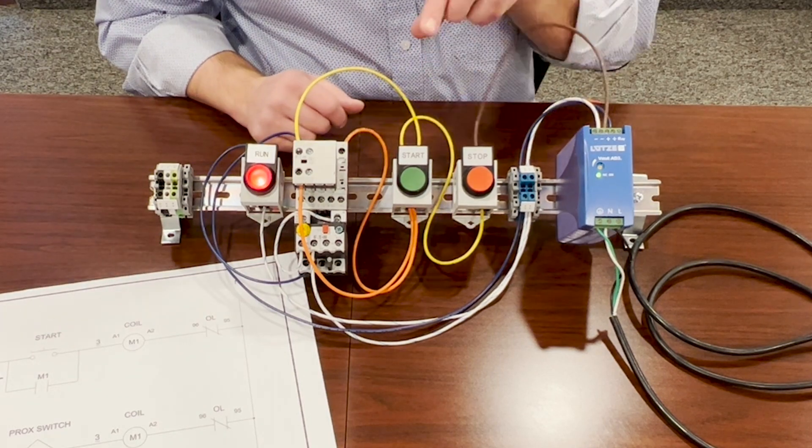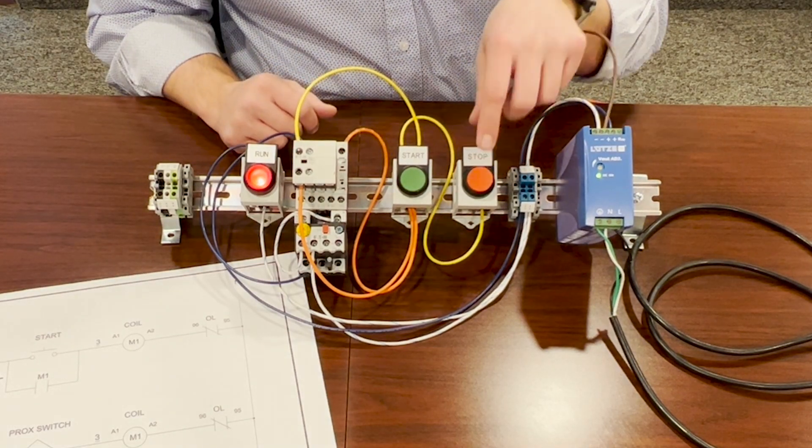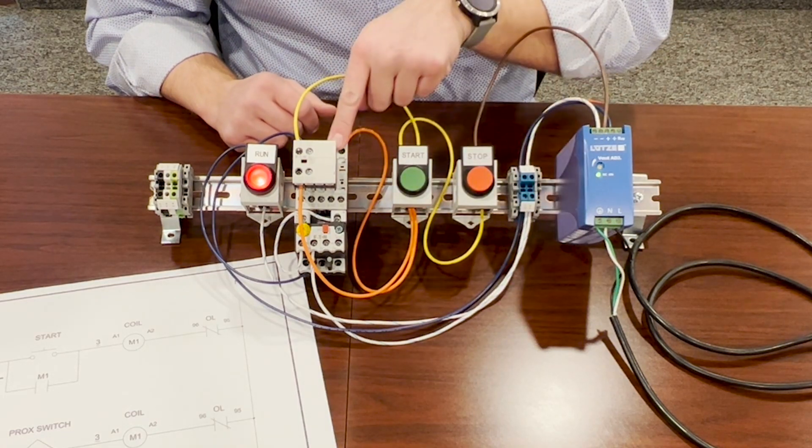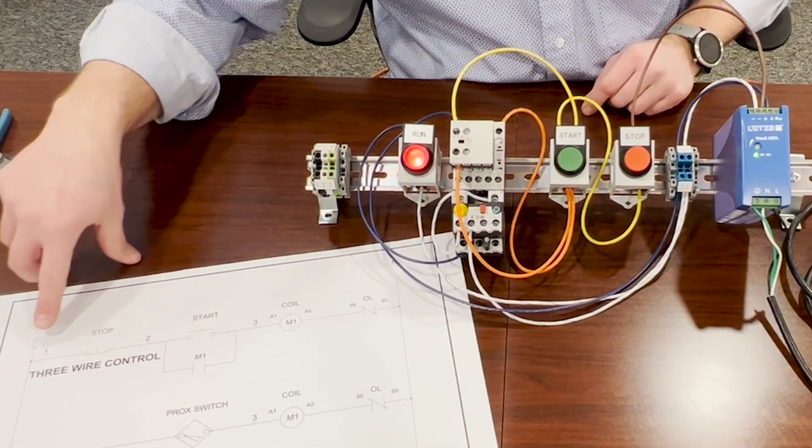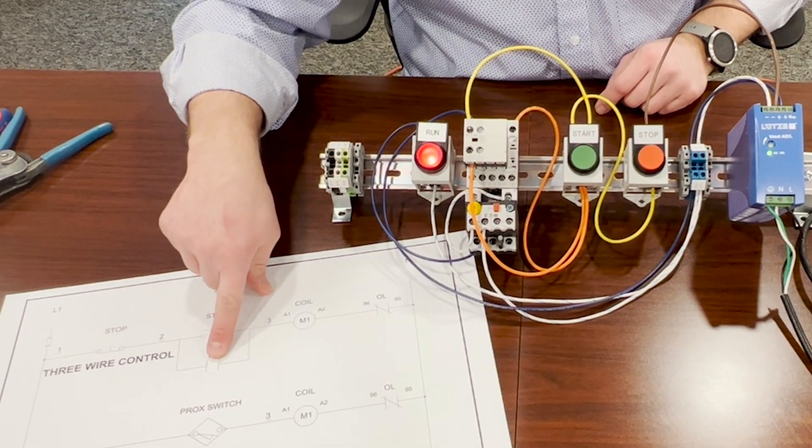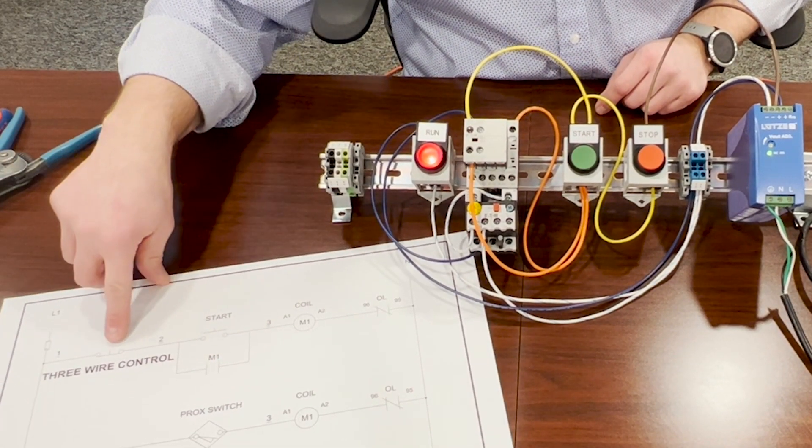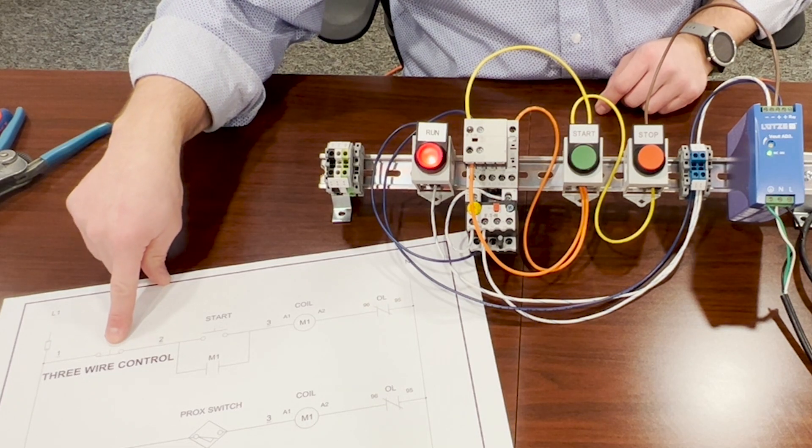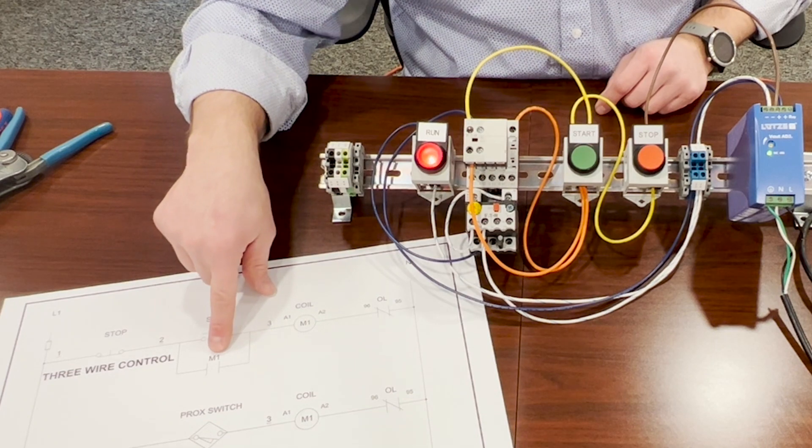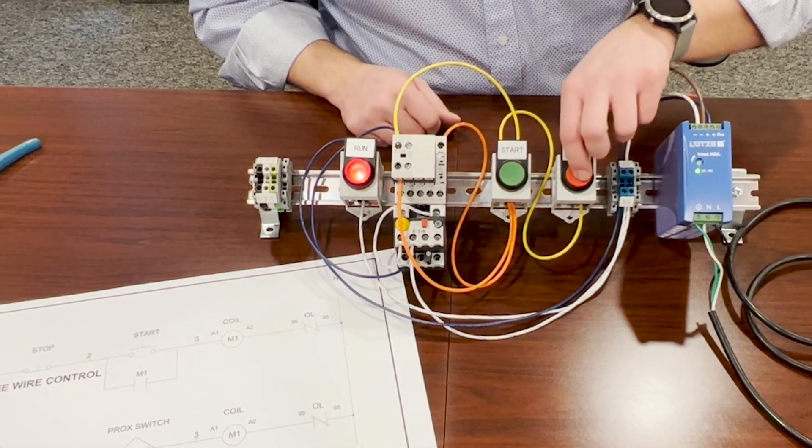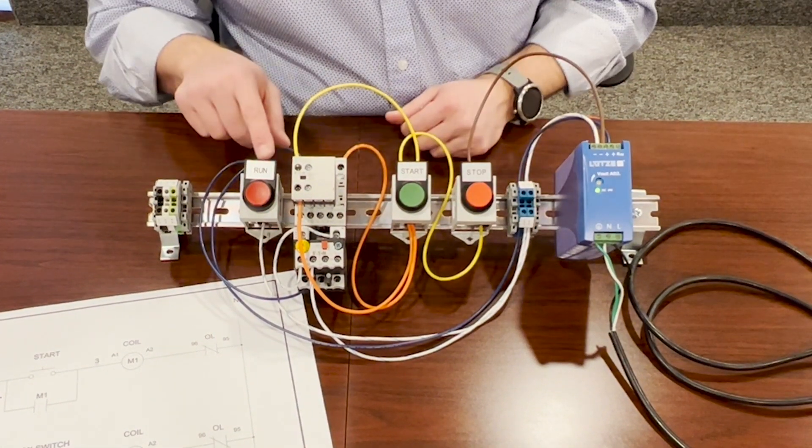So when we hit the stop button, it's going to break the 24 volts that's going to the coil and it will allow this to shut off. So on the drawing, right now this is closed. But when we push this button, it's going to de-energize the motor starter and this contact will open back up. So when we push the stop, our light turns off.